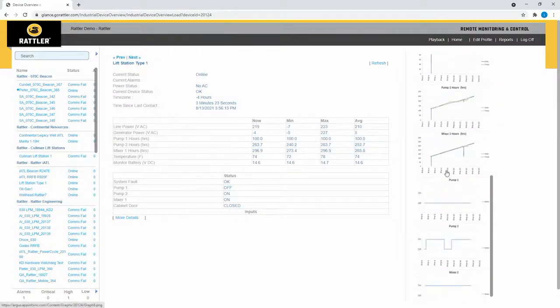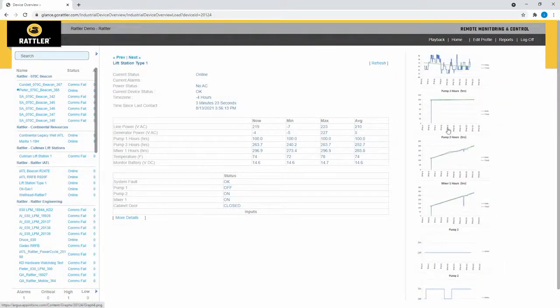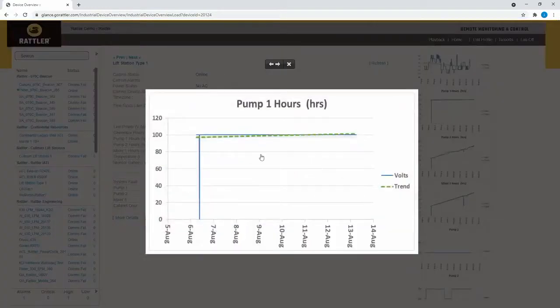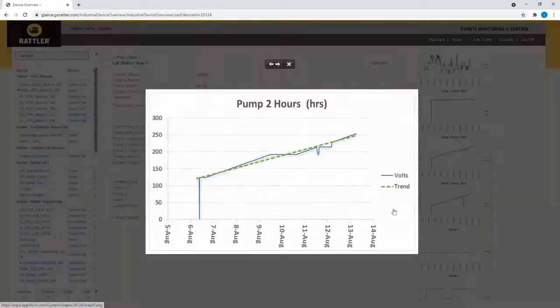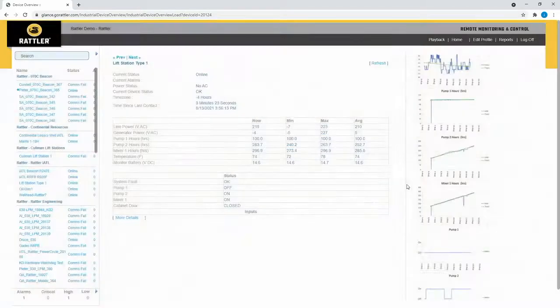It gives some quite interesting information about utilization. For example, this is the pump 1 hours graph, which shows a pretty horizontal line. Pump 1 never goes on. That indicates a fault if you're trying to do load leveling between the two pumps, because pump 1 never goes on. But pump 2 went on with a pattern like this. The slopes of these graphs indicate utilization, and the trend line shows the utilization percent of how much these pumps are being utilized.